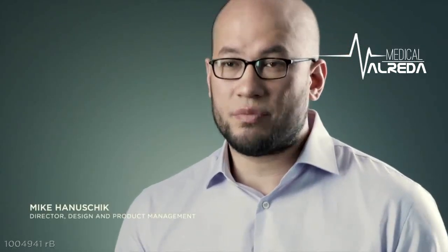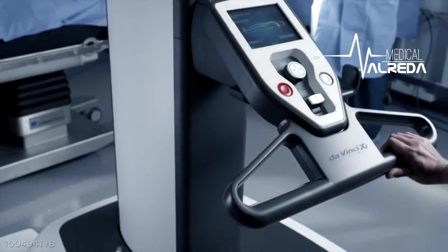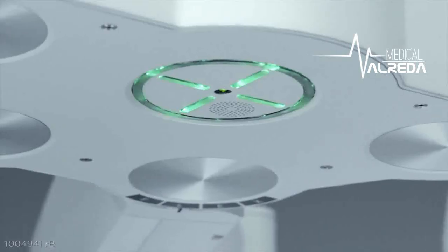Making the system much easier to use was a primary focus of developing the da Vinci Xi. Docking is facilitated by a laser targeting system — point the endoscope at the surgical site, press the targeting button, and the system will configure itself into the optimal position for the procedure.